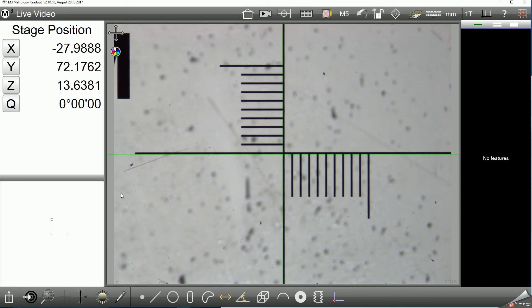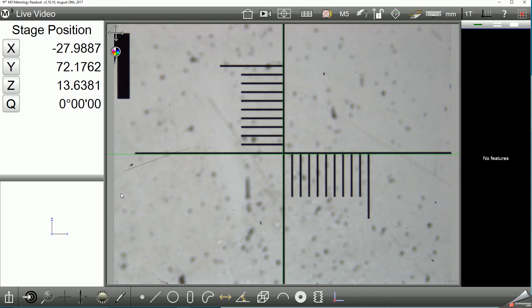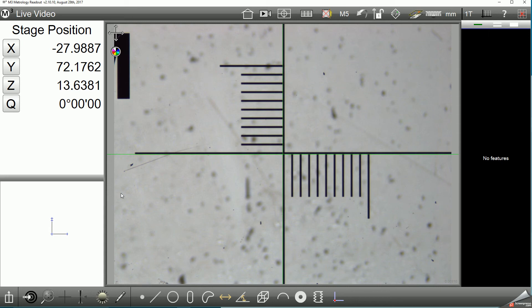The SLEC is collected in one axis at a time. In this video, we will execute the SLEC routine in the X axis, but this procedure can be repeated for the Y axis as well and the Z axis when using an appropriate calibration artifact.